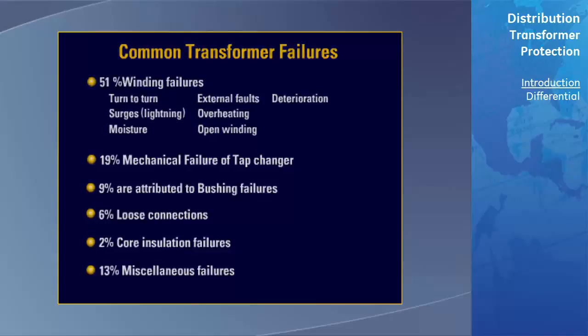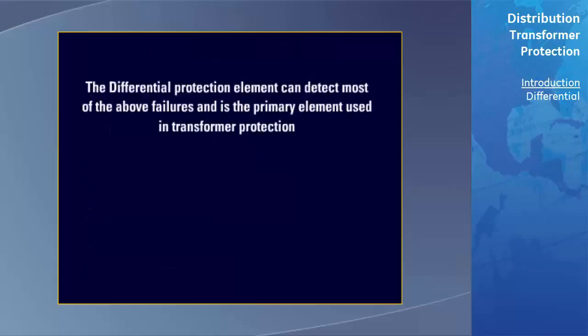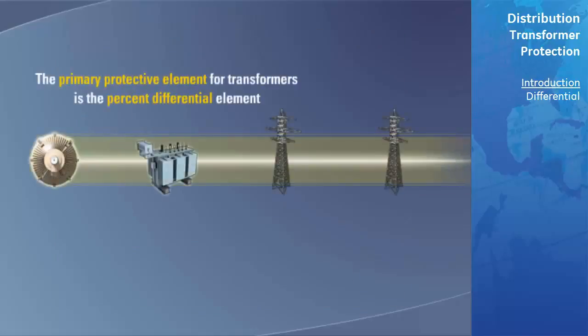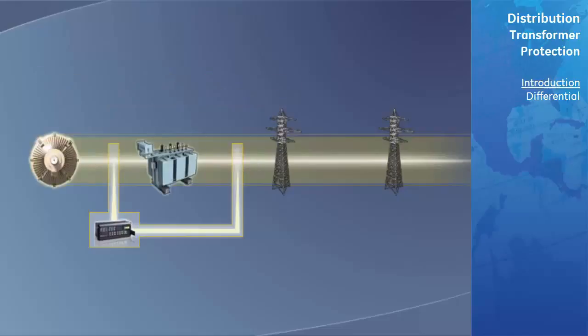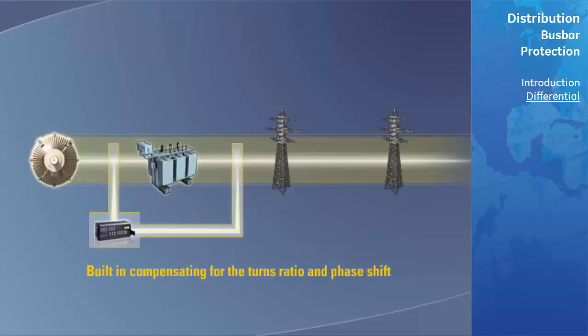The percent differential protection element, which is considered the primary protective element for transformer protection, can detect most of these failures. Differential protection. As stated, the primary protective element for the transformers is the percent differential element, which compares the current entering and leaving the transformer. Modern microprocessor-based transformer percent differential relays, such as the GE Multilin T35, T60, and SR745 relays, have built-in compensation for the turns ratio and phase shift, and so neither of these topics will be addressed. For further information on the percent differential element's theory of operation, please reference the percent differential section of this course.